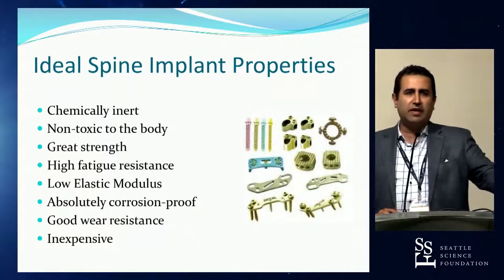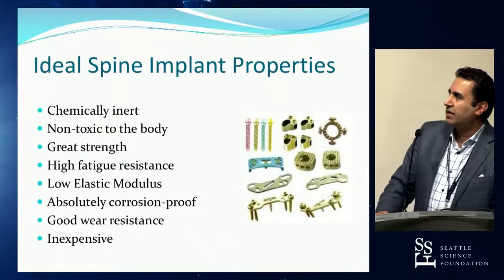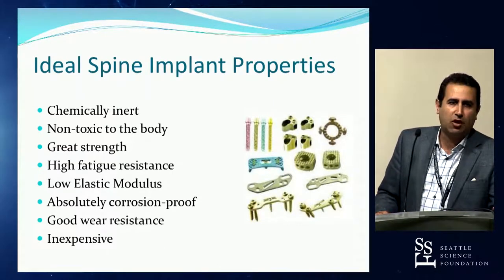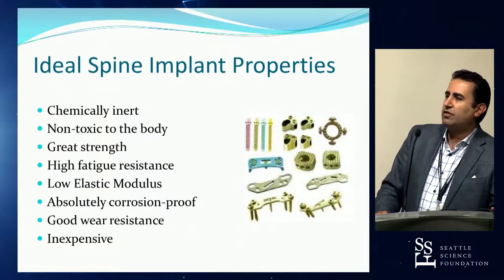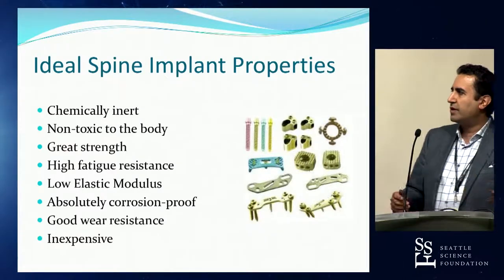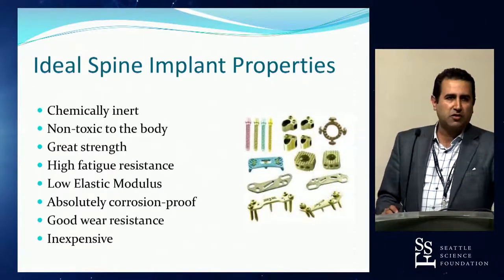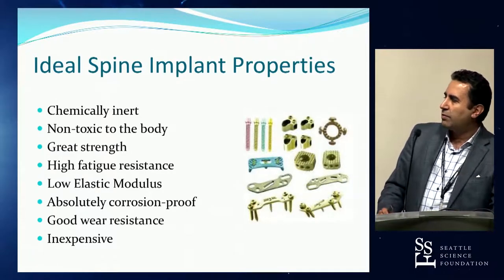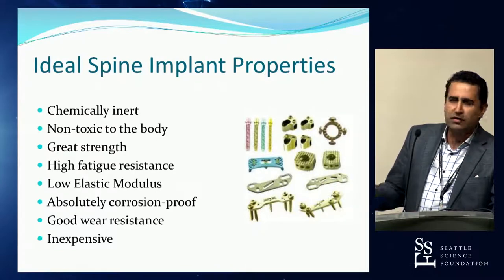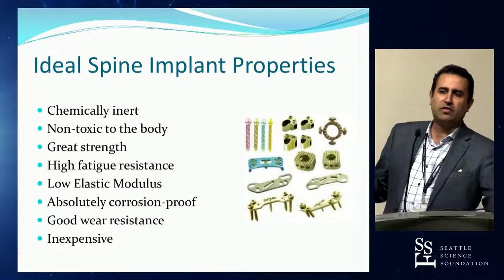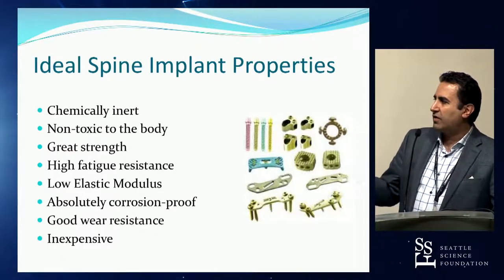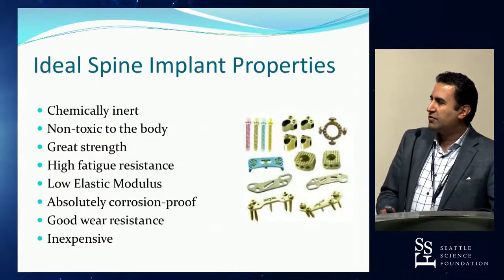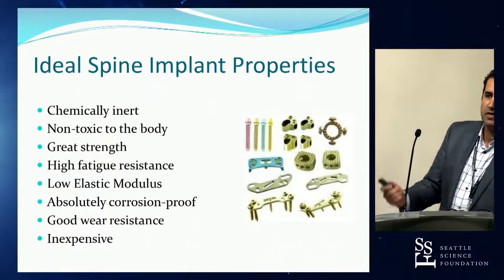The ideal implant properties: it must be inert — it can't leach or become toxic. It must be strong enough to achieve its goals, resistant to many load cycles, and have a low elastic modulus approximating bone. It must resist corrosion, lasting decades without oxidation, resist wear, and most importantly be inexpensive enough to use.